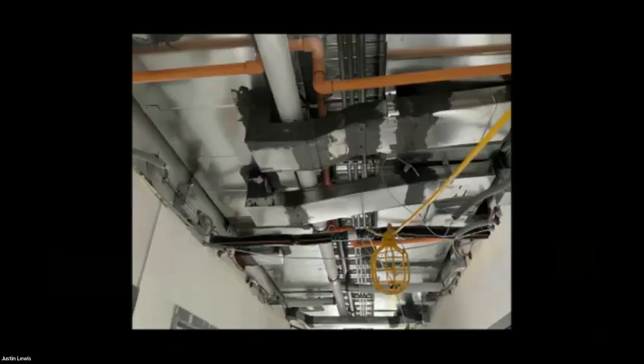So take a look at this distribution system. This is an ERV system feeding outside air to 3 levels of living units. Very low flow, 50 CFM. What kind of pressure loss do you think we can expect from all of these transitions? Probably quite a bit. Well, let's look at the one behind it. It's even better.